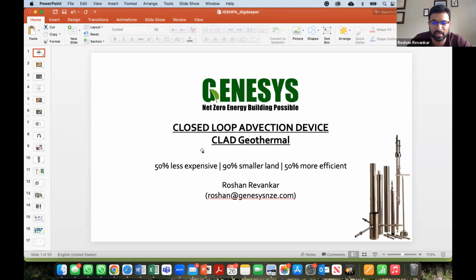So I'm assuming the question is, can these be used for retrofits? I believe so. Yeah, absolutely. For both retrofits and existing water wells: if there is an existing water well that just has a pump and all it's doing is pumping water out of the ground for domestic water use, instead of just doing that, you could install CLAD and have the same pump at the bottom of it, or maybe a different pump in this case. It can be used for existing applications that have wells, or where you probably need to drill more wells. And on the groundwater piping side, if you can imagine, you don't have several boreholes that need to be connected, so the trenching work is going to be much less. So it fits really well for retrofit applications.